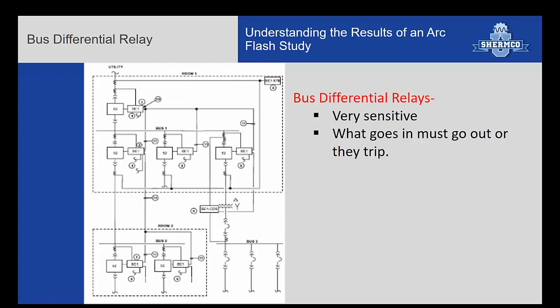On medium voltage, we see bus differential relays, and they greatly reduce the arc flash on the main bus of the switchgear. With the bus differential, here I have a red arrow. Any current coming into this bus must be leaving at one of these blue arrows. So the relay looks for the sum of what's coming in to equal the sum of what's going out, and it can be set very sensitive to trip if those don't add up. So if a fault happened in this zone, in between the CTs, then you could clear this bus very quickly. This is a big benefit to reduce incident energy, especially when you're racking breakers in and out on medium voltage gear.